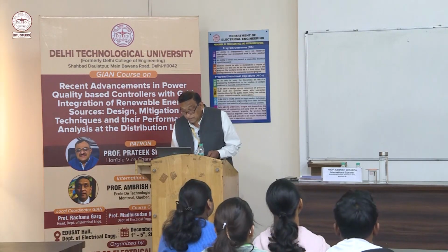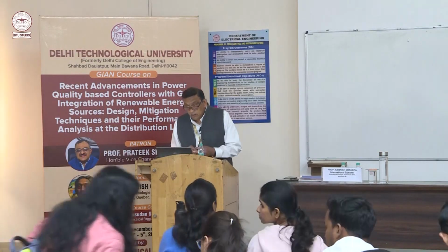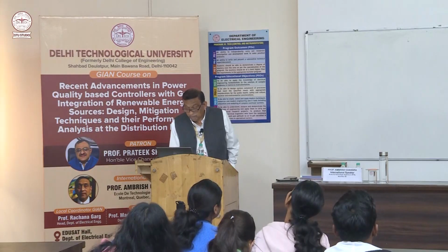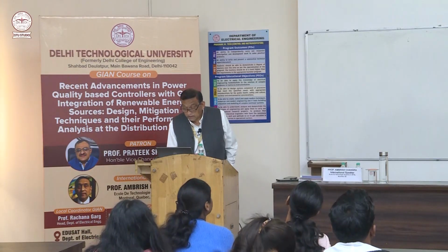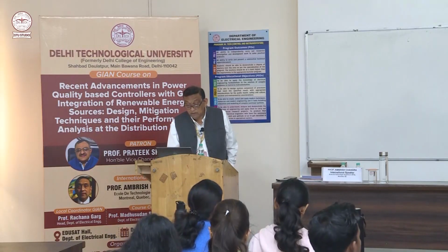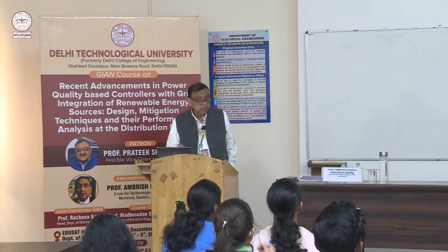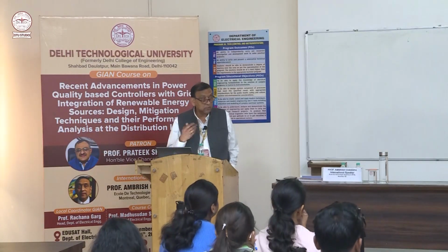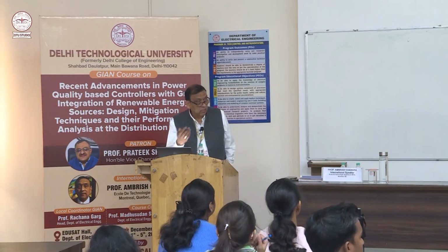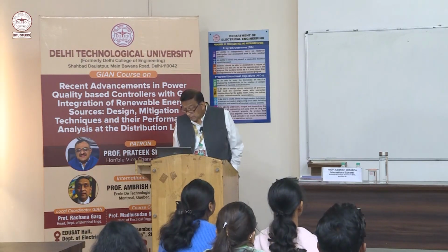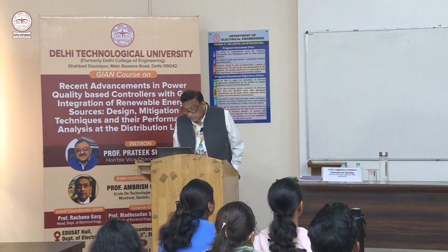Here you can see there is a phase shifting between the dd0 transformer, with 0-degree phase shift, and dy1, which has 30-degree phase shift. So that's why there is a phase shifting here and here in instantaneous voltages. So for the problem of circulating current, that is why we were using interphase transformers. This we have already discussed.